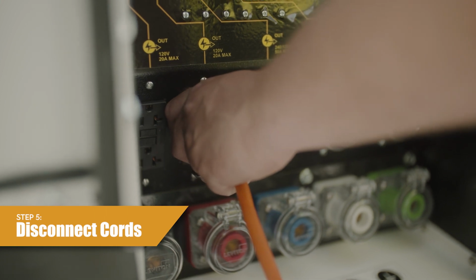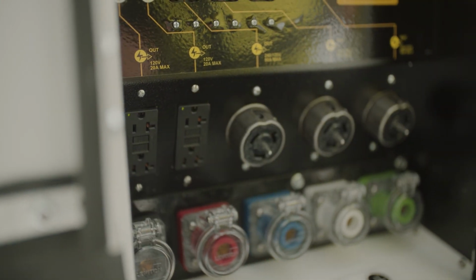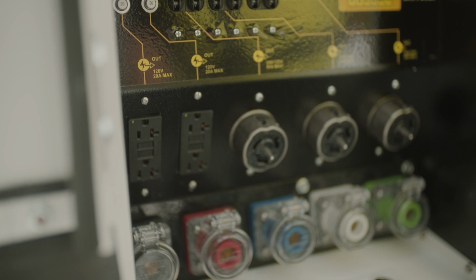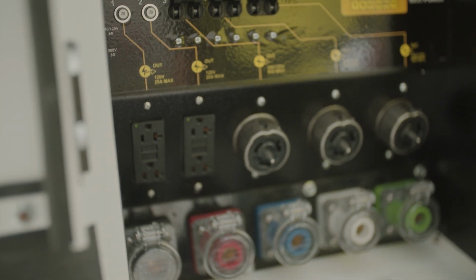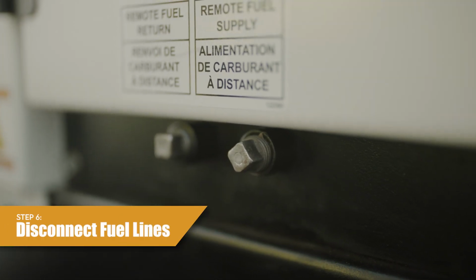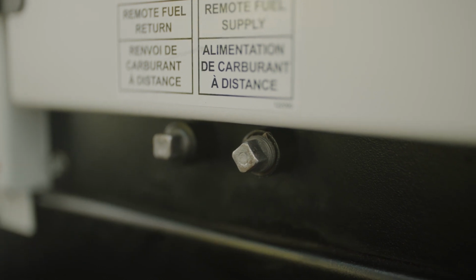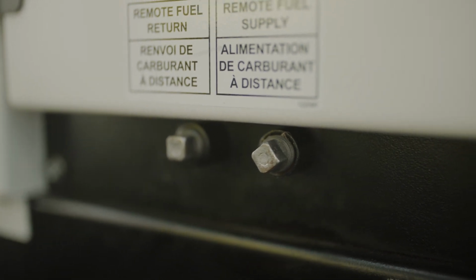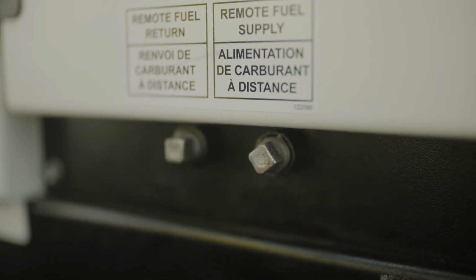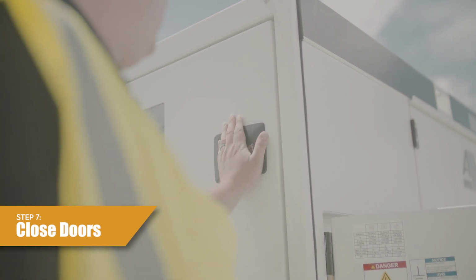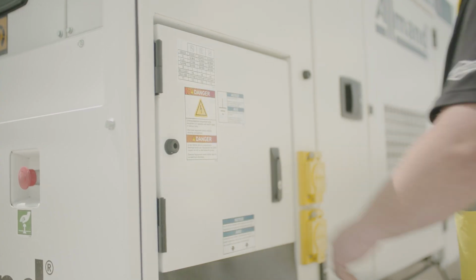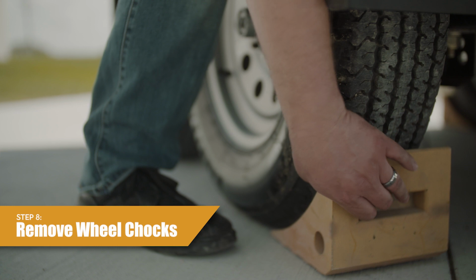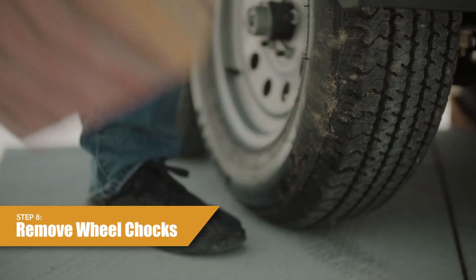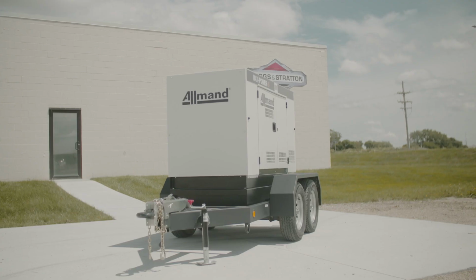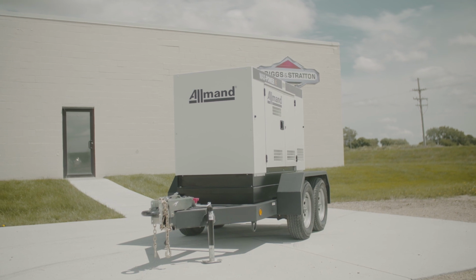Step 5. Disconnect any power cables or cords from the AC output panel and store cables and cords in their proper location. Step 6. If using this option, disconnect any remote fuel lines and reinstall fuel line plugs. Step 7. Close the control and AC output panel doors. Step 8. Remove wheel chocks. Step 9. The unit is now ready for transport.